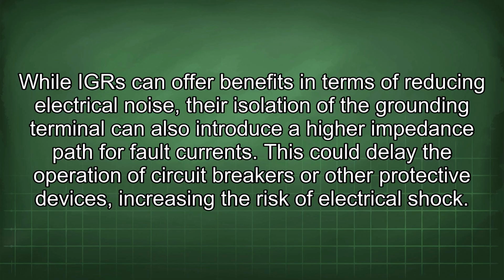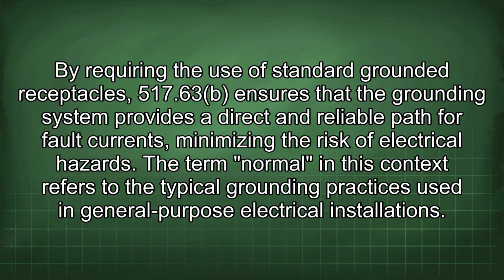This could delay the operation of circuit breakers or other protective devices, increasing the risk of electrical shock. By requiring the use of standard grounded receptacles, 517.63 ensures that the grounding system provides a direct and reliable path for fault currents, minimizing the risk of electrical hazard. The term normal in this context refers to the typical grounding practices used in general-purpose electrical installations.